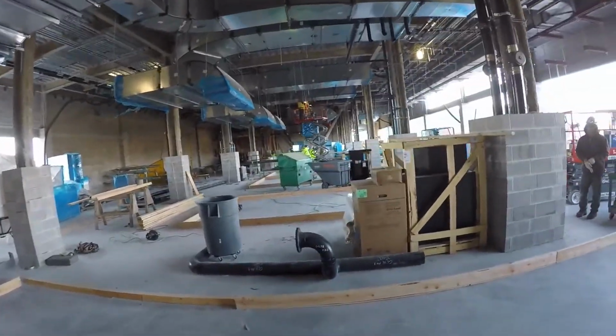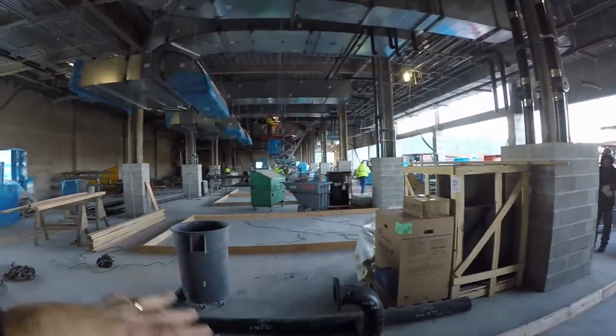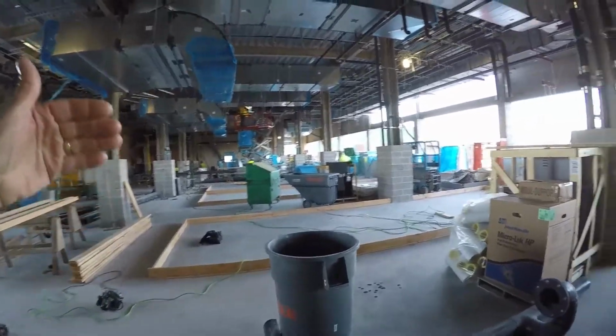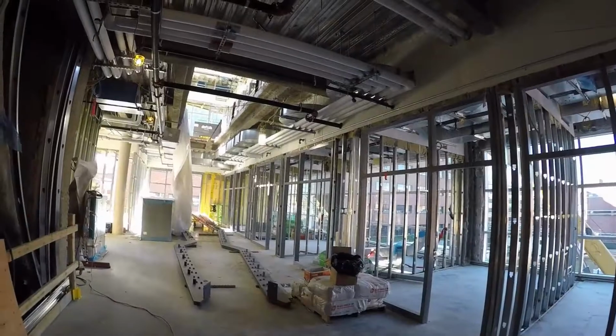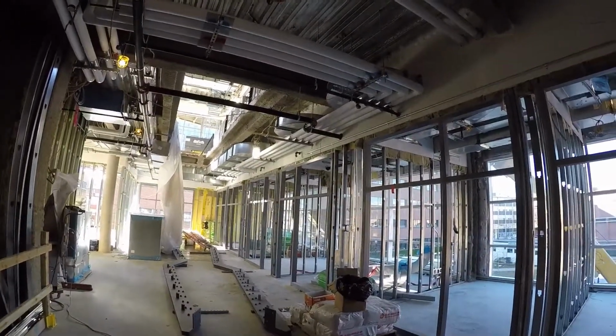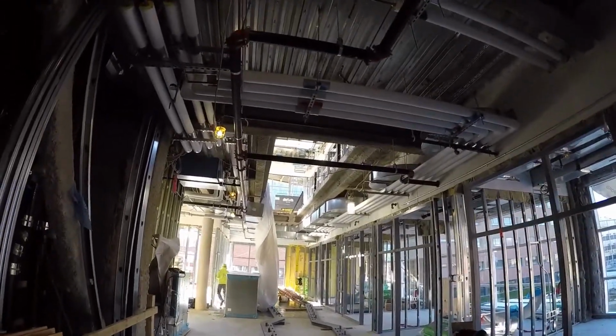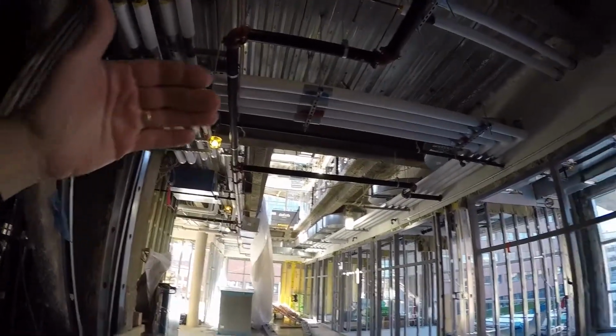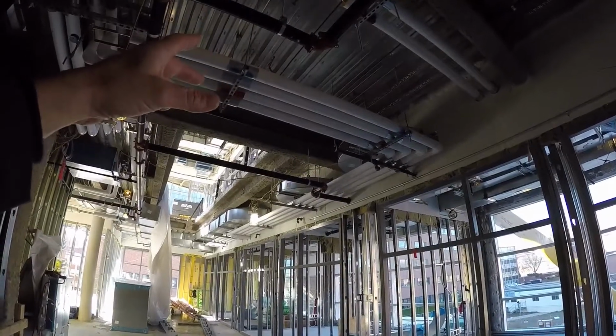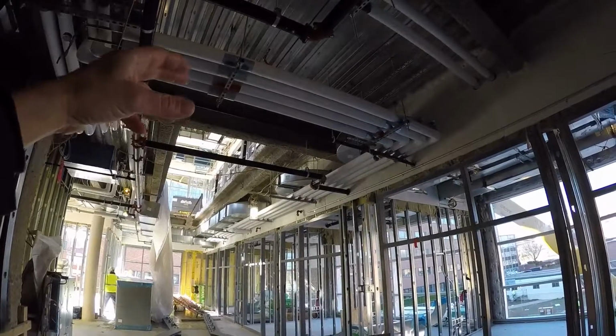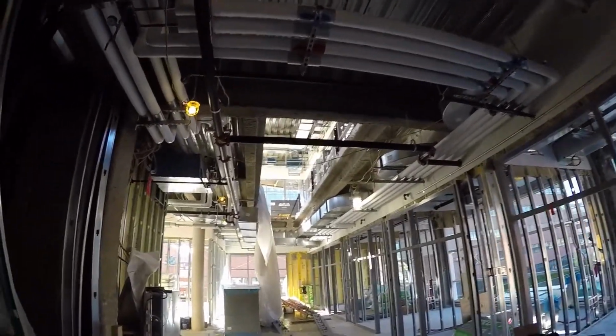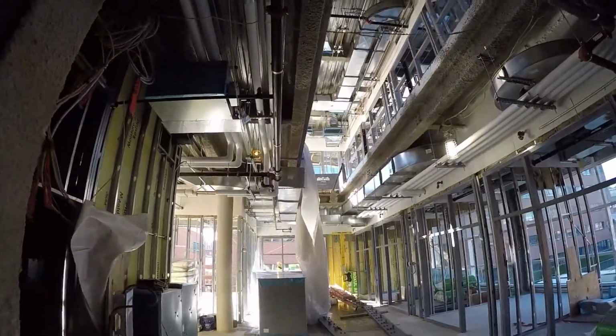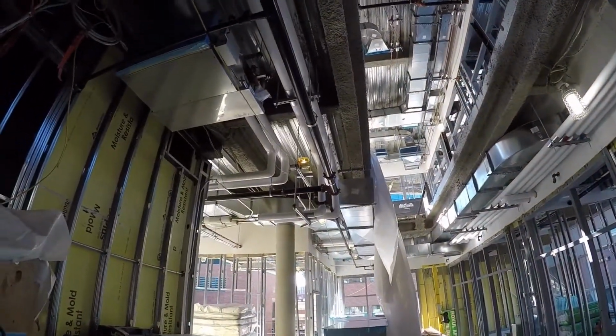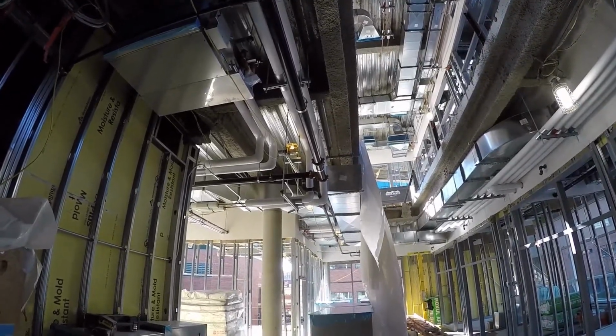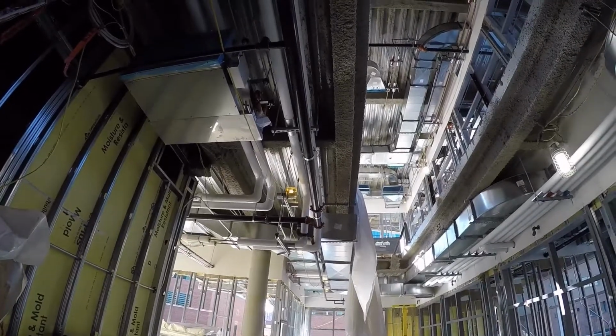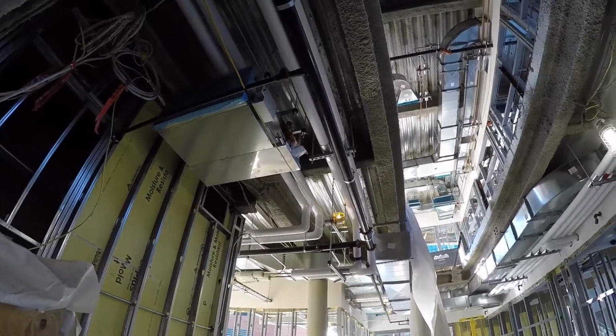Very windy actually up here today. So they're trying to do as much of the mechanical work as possible ahead of the air handler installations. So we're looking at, on the pads here, 1, 2, 3, 4 locations. This particular building has some of the most high-tech systems that you'll find. One of the systems is what we call a 4-pipe heating system. When you look up to the rack, blue stands for the chilled water and red stands for the heat. So there's a supply and return for the heat and a supply and return for the chilled water. So the units have 4 pipes going to them. It's called a 4-pipe system. That means in the shoulder seasons, the equipment has the chance to go from cooling to heating all in the same day, whereas with the classic 2-pipe systems, it's either in a cooling mode or in a heating mode.